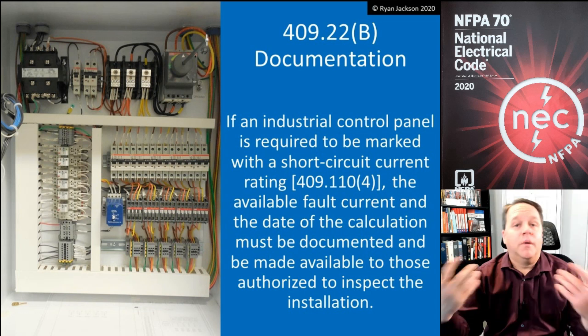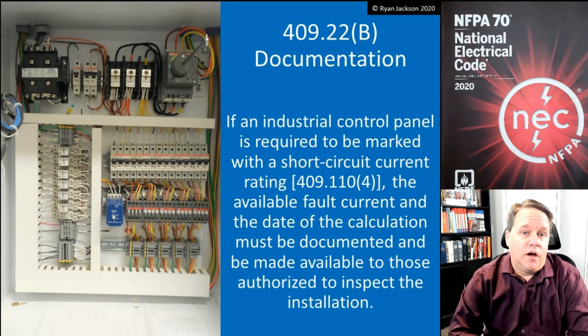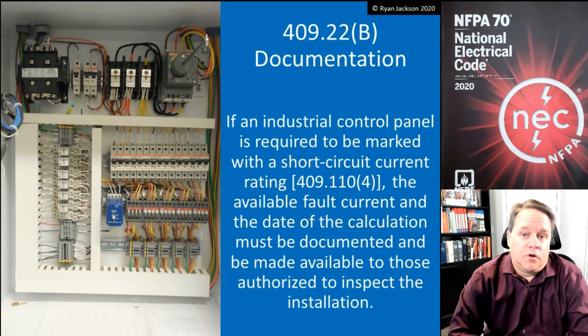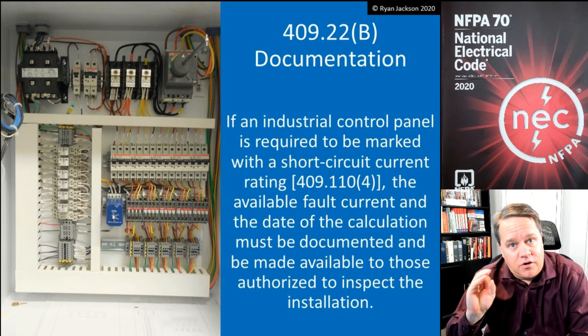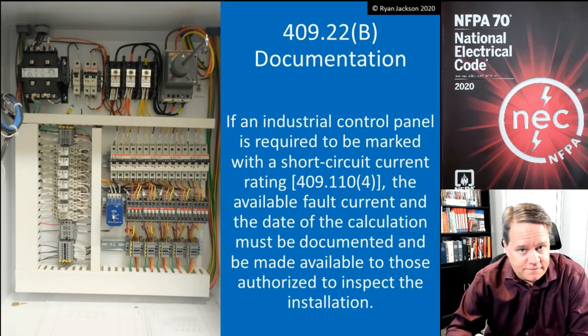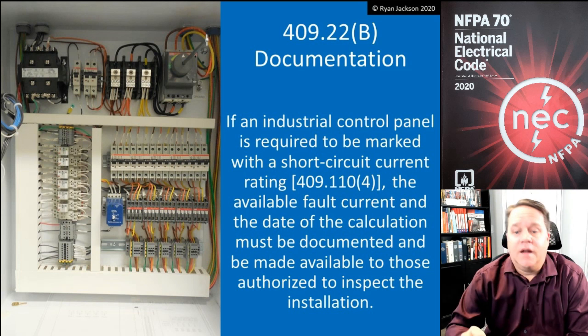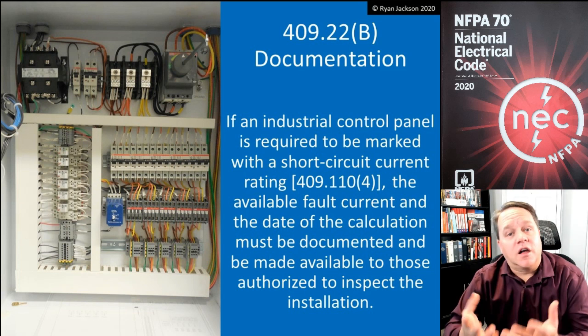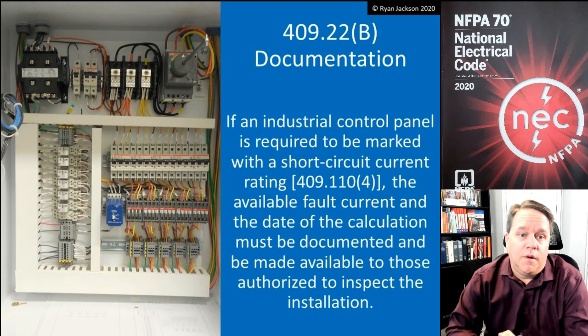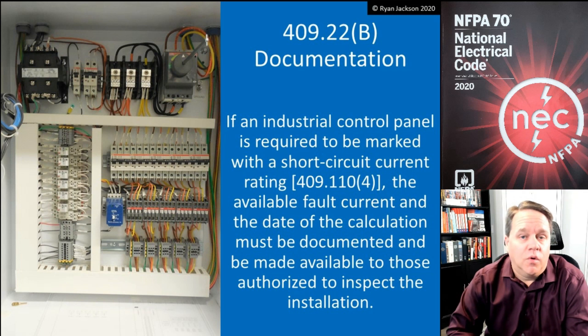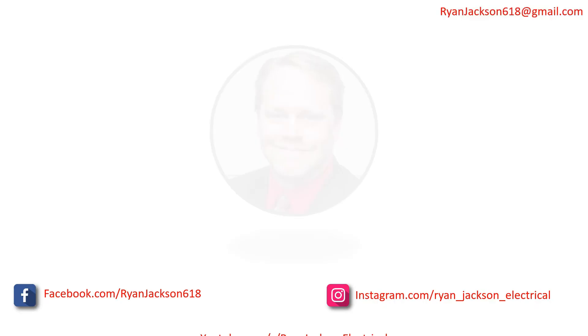That means it will probably need a field evaluation to determine the short circuit current rating, the available fault current will have to be calculated, documented, and made available to anyone who needs that information.